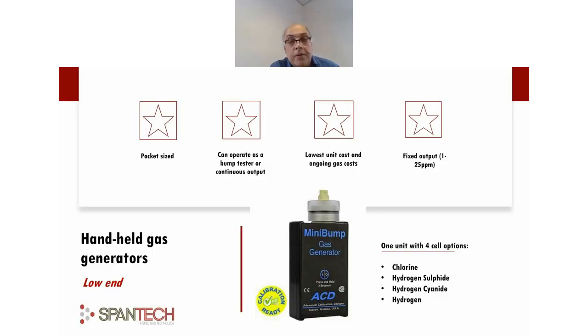So as an example of the handheld generators, we tend to call them the mini bump because they're used for bump testing. But as I said, you can change the cell and you can get a continuous output from them. To give you an idea of the size, basically that mini bump unit will fit into the top pocket of my shirt. So it's very small. Of the gases we're talking about today, it will only do chlorine though. It will additionally do some of the other gases like hydrogen sulfide, hydrogen cyanide, and hydrogen, but it's not an ozone or chlorine dioxide generator or bump tester.